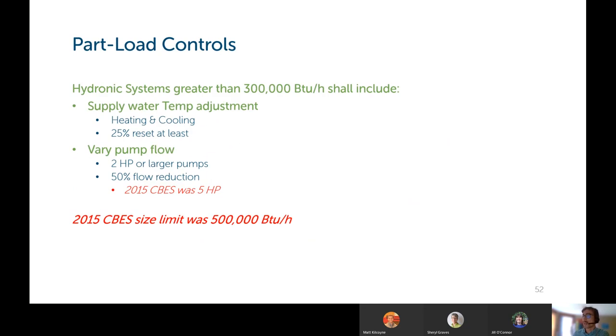Part load controls: any hydronic systems that are greater than 300,000 BTU per hour shall include supply water temperature adjustments of both the heating and cooling water supply, and you must reset those at least 25%. The old limit for systems in the previous code was 500,000 BTU per hour, so that has now been reduced. You must vary pump flow for any pump 2 horsepower or more, and you must do at least a 50% flow reduction. The previous code had that requirement for pumps 5 horsepower or greater. So that horsepower rating has been reduced for the 2020 code.